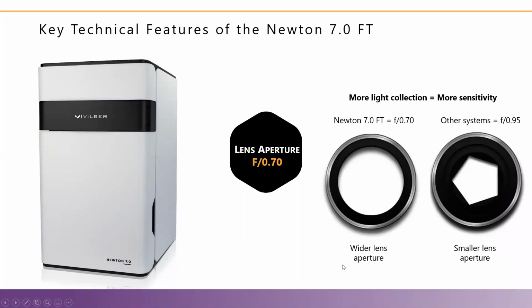Another benefit is the wide lens aperture. The main function of a camera lens is to collect light, which is very important in optical imaging. The lens aperture represents its capability to collect as much light as possible in a given period, and its sensitivity is usually expressed by the range of f-stops. The smaller the f-stop number, the larger the aperture. A lower f number denotes a greater aperture opening, which allows more light to reach the CCD sensor. The aperture of the Newton lens is 0.7, providing the best sensitivity and speed, which allows us to reach the lowest limits of detection compared to standard systems that have a smaller lens aperture.